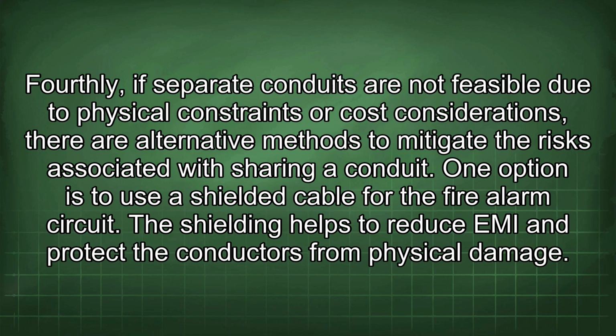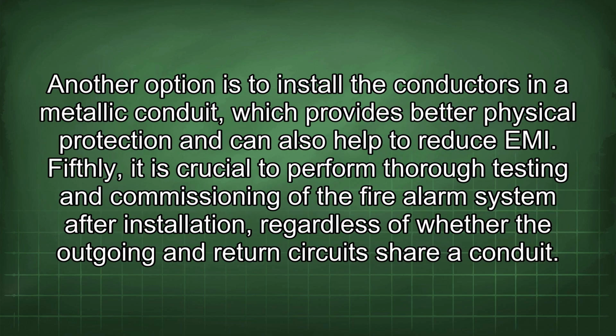Fourthly, if separate conduits are not feasible due to physical constraints or cost considerations, there are alternative methods to mitigate the risks associated with sharing a conduit. One option is to use a shielded cable for the fire alarm circuit. The shielding helps to reduce EMI and protect the conductors from physical damage. Another option is to install the conductors in a metallic conduit, which provides better physical protection and can also help to reduce EMI.